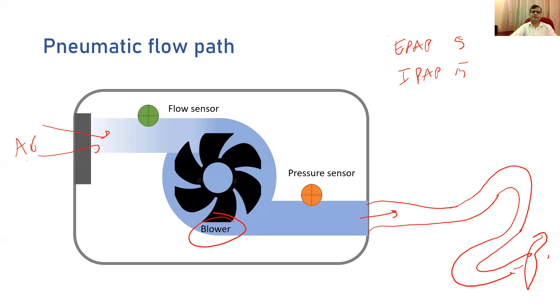So you have a pressure sensor over here, and the flow sensor will sense what amount of flow is coming in. So the blower can decide how much flow, and the blower can very efficiently generate and achieve that pressure within a fraction of a second. That is the intended purpose of these portable devices, to be used in the domestic environment in sleep disordered patients, to generate these pressures when the patient is breathing at different flow requirements. So the machine is capable of delivering just that. It's quite good devices for that purpose.